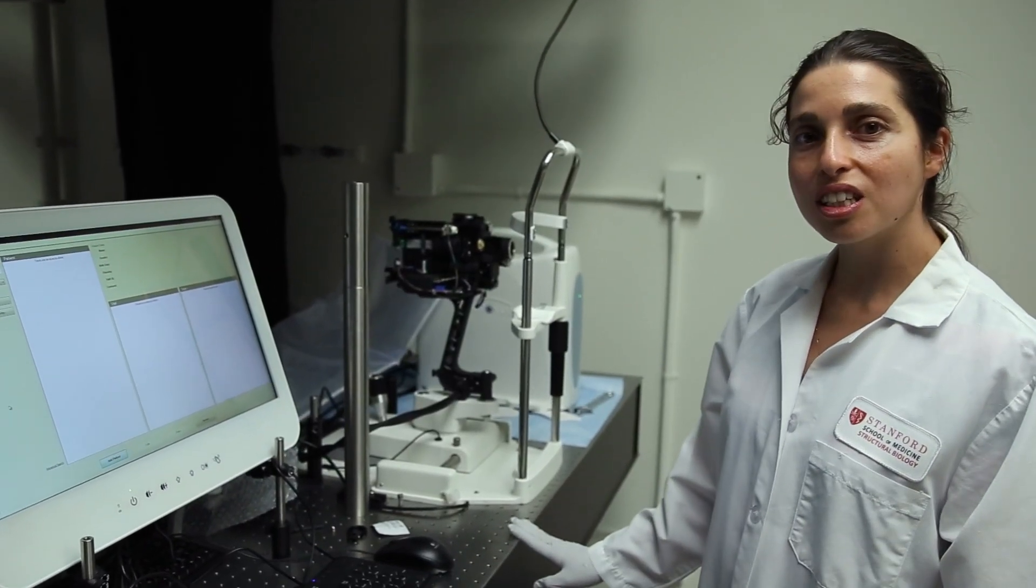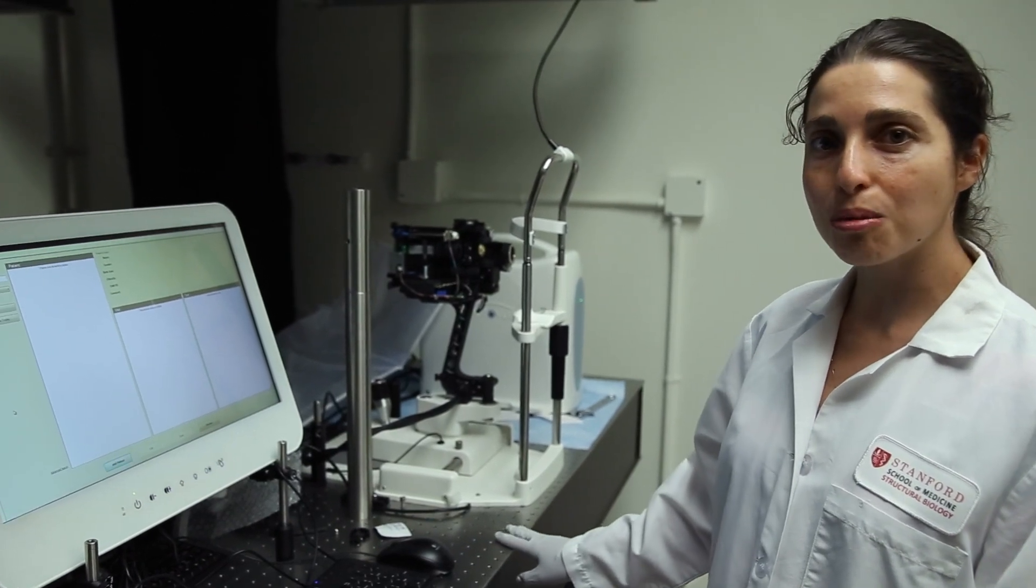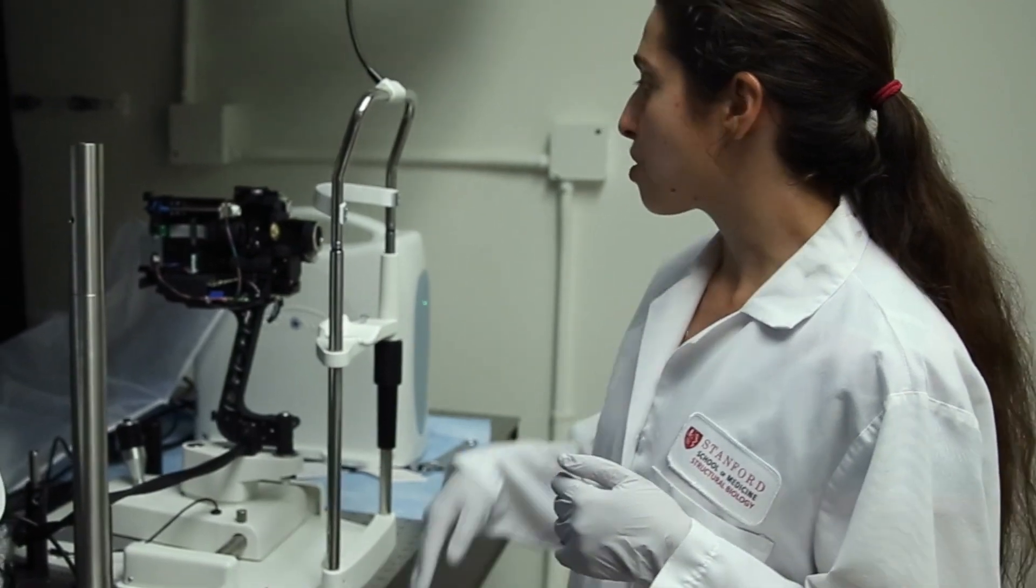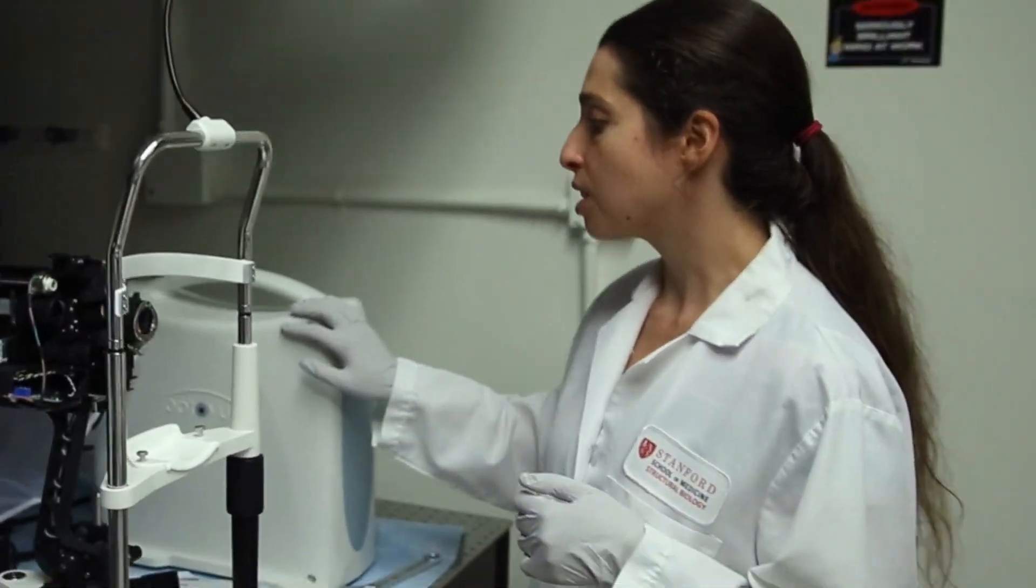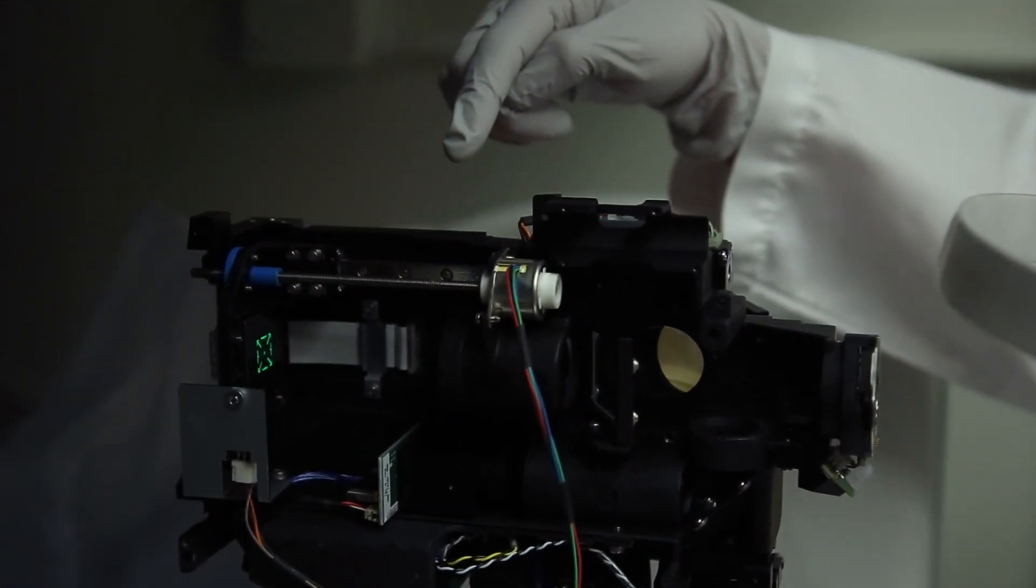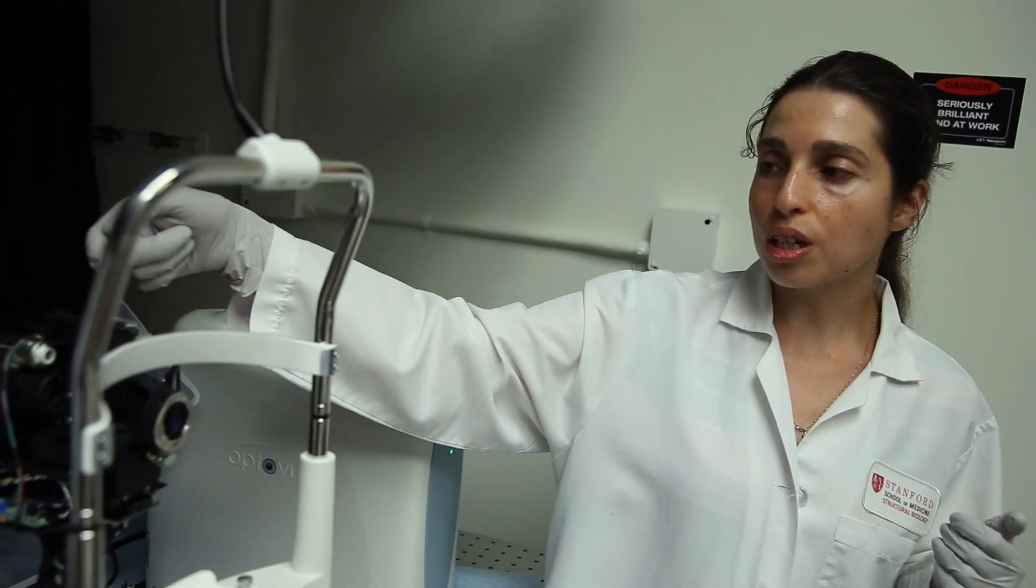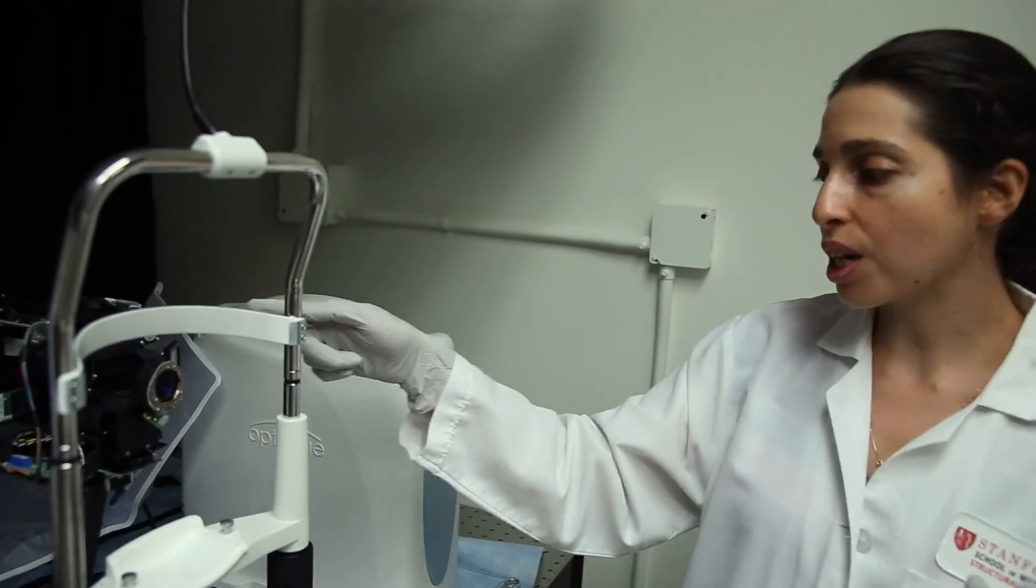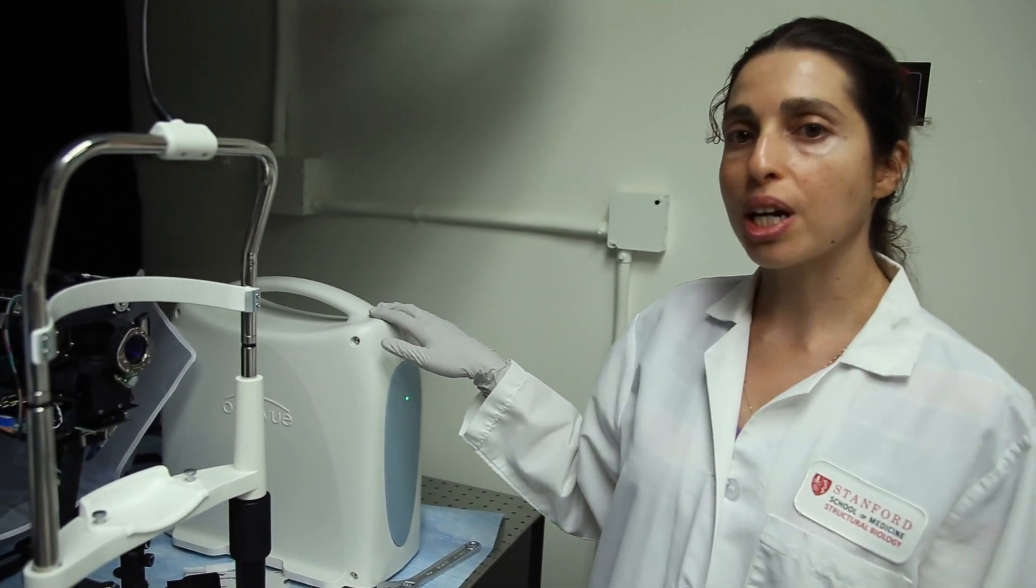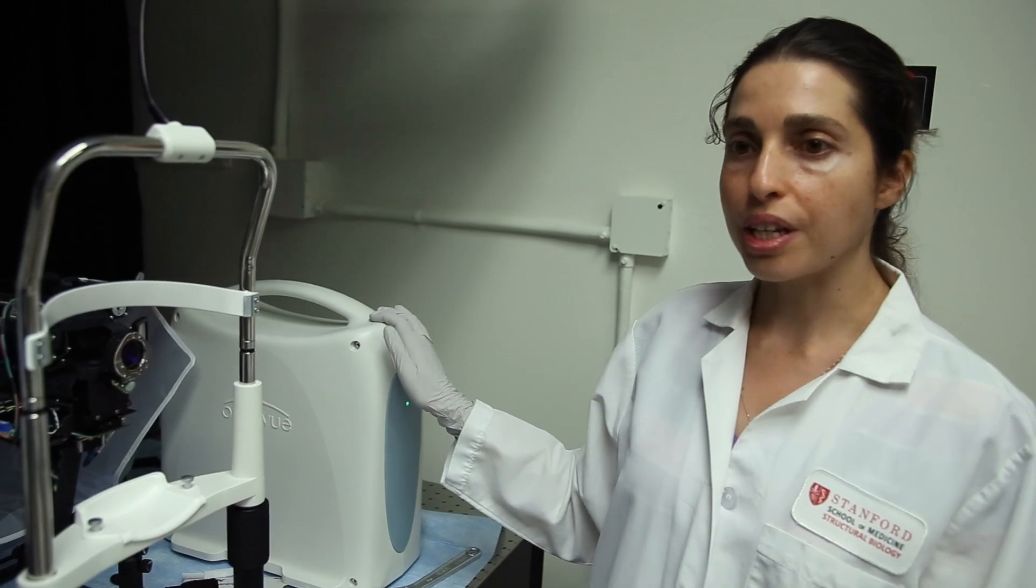This is a clinical OCT, an optical coherence tomography system to image the retina. What it does is there is a laser here and the light from the laser goes through this fiber. The light goes here into the eye, comes back into this, and here is a detector that shows the backscattered light and creates an image.